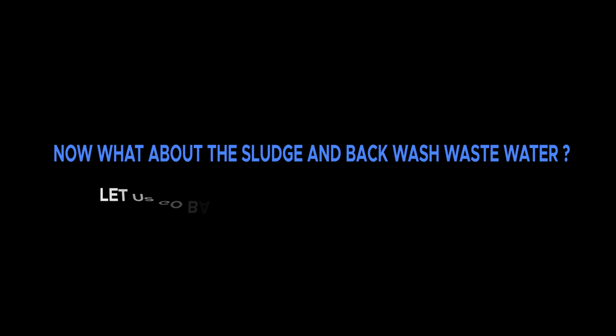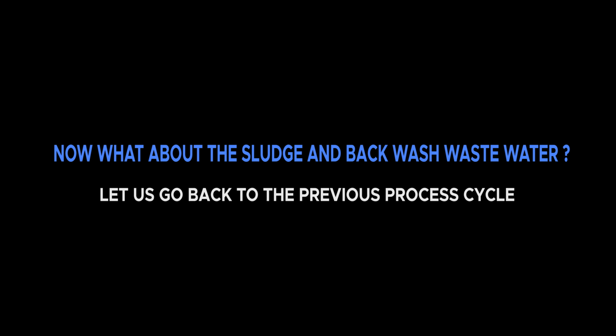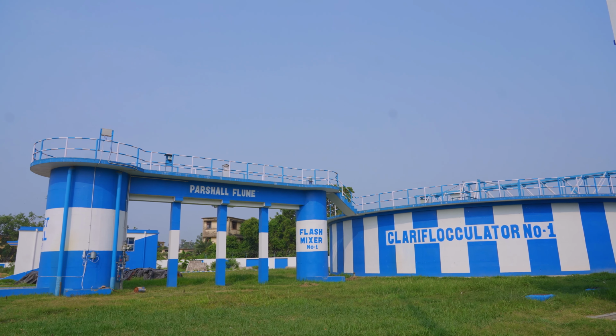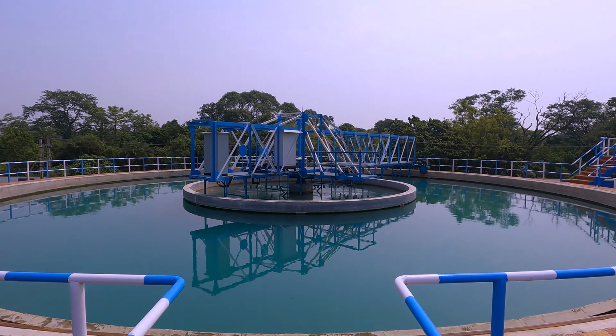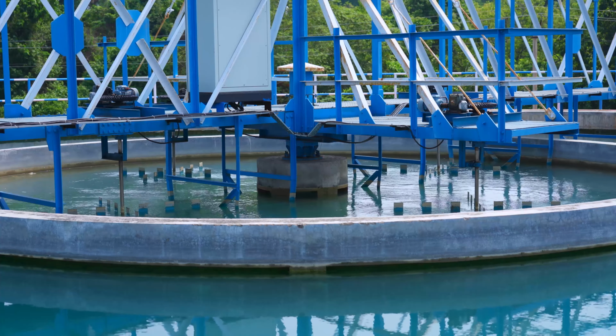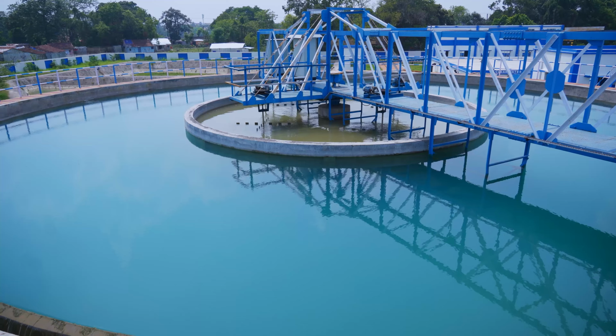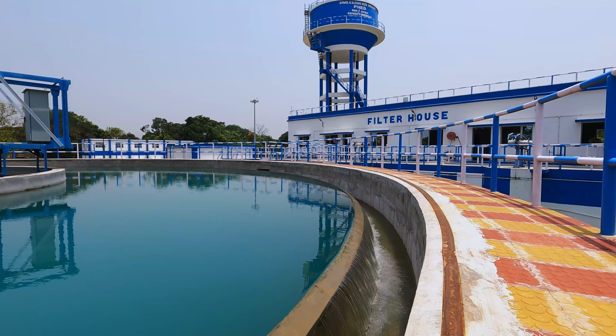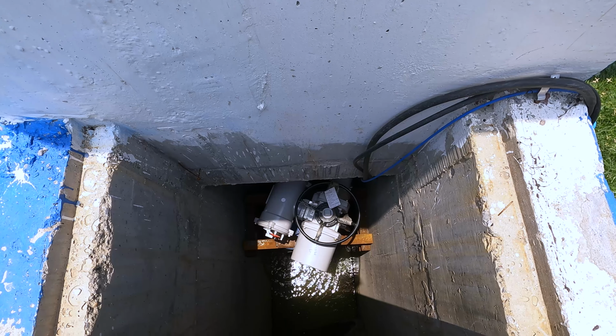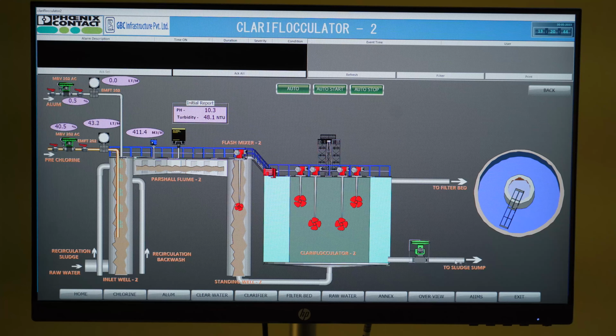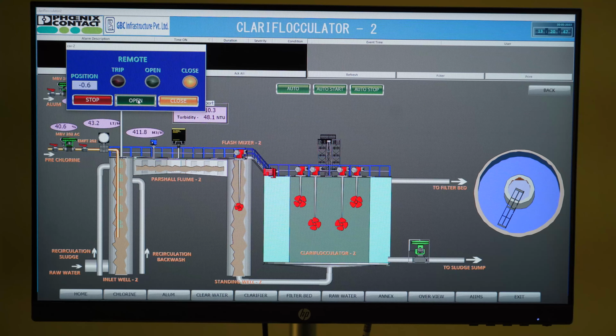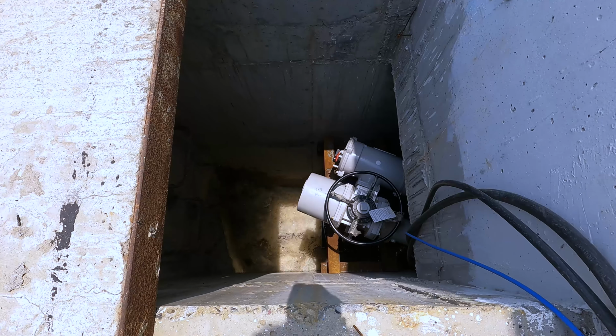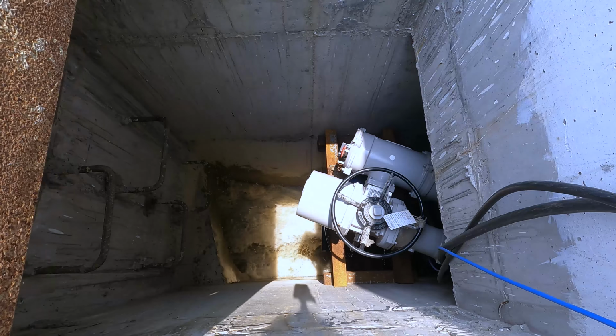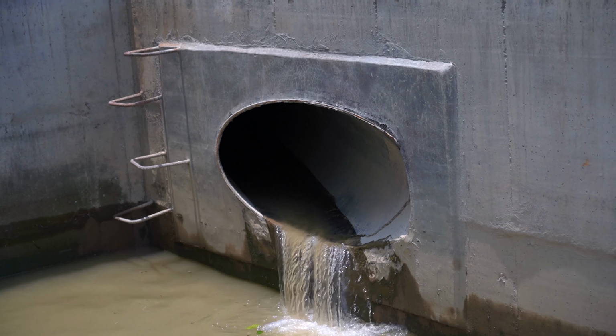Now, what about the sludge and backwash wastewater? Let us go back to the previous process cycle. As the clarification process continues, the sludge settles down to the bottom of the clariflocculator. So, from time to time, the sludge from the bottom of the clariflocculator has to be cleaned. The motorized gate valve fitted at the bottom of the clariflocculator is opened by the operator by a click of a button. The mixed sludge water comes out and goes to the sludge collection sump.